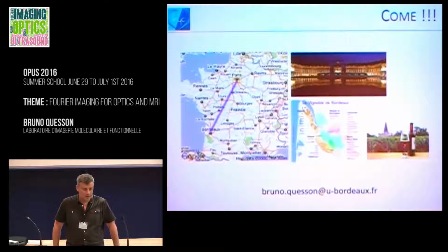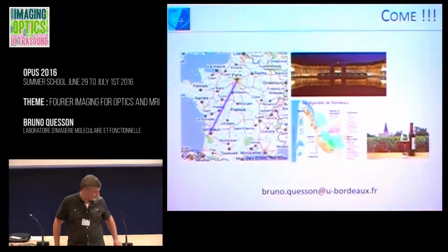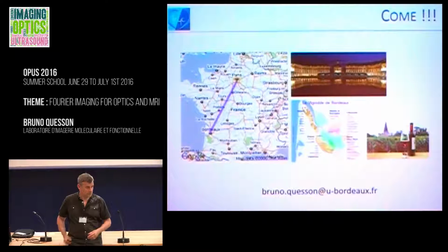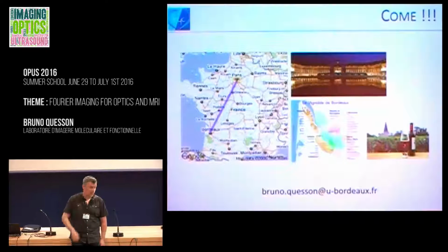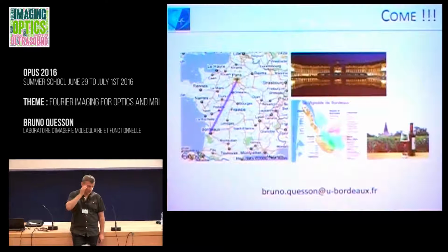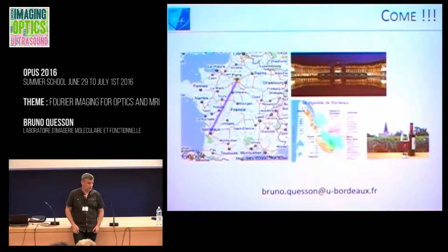I understand. You can use, for example, optic sensors, that are optic thermometers that are invasive. You can put it for calibration purpose at the beginning. You can do that. And we did that, and we see a very good correlation, a very good correspondence between the temperature measurement that you get from MR and from your device, which is implanted. You can do that, but it's not the idea. This is the idea to calibrate. Once you have calibrated, the idea is to insert nothing into your patient.